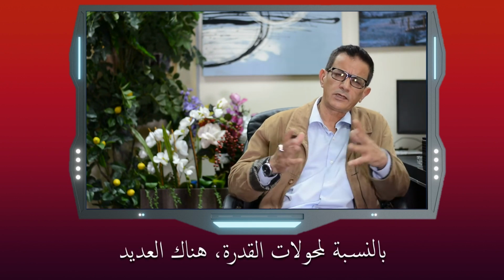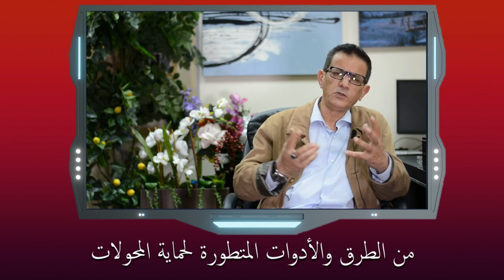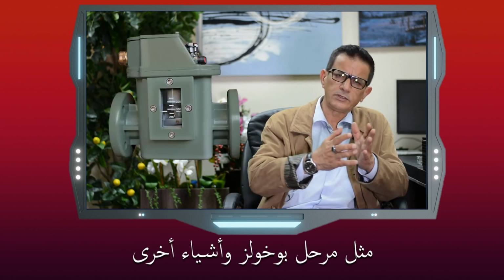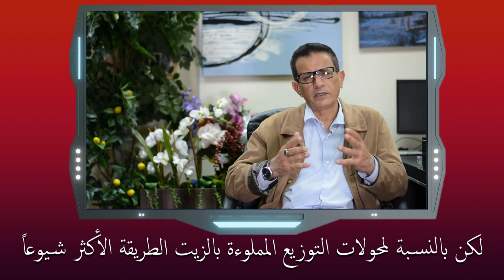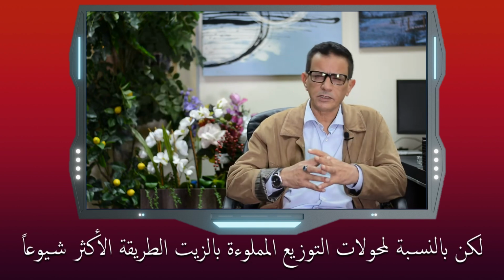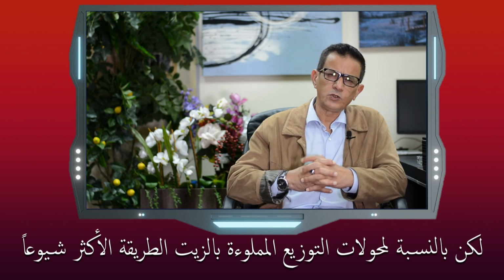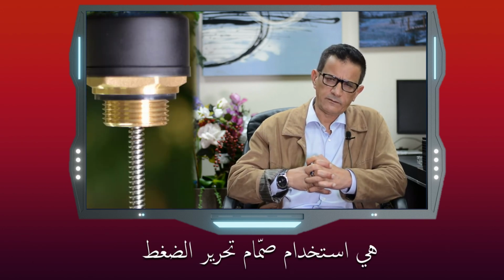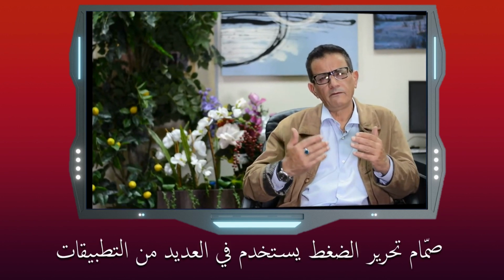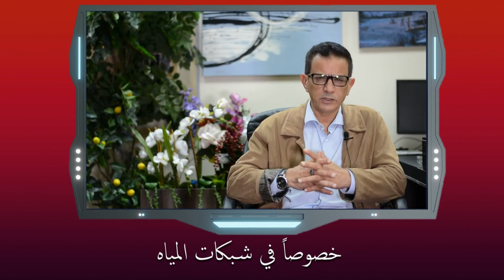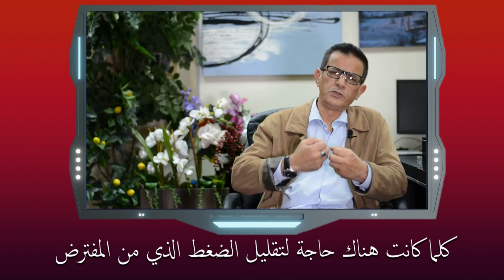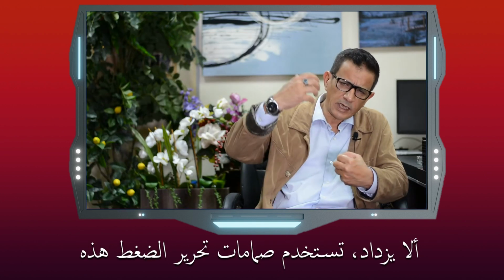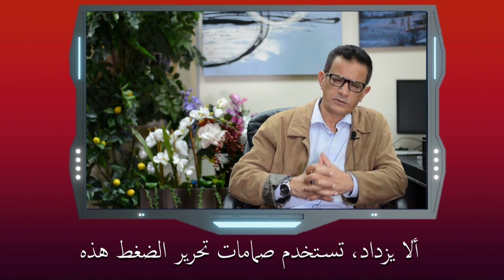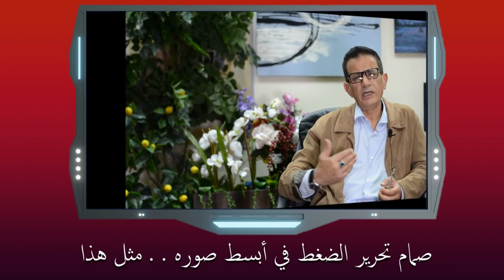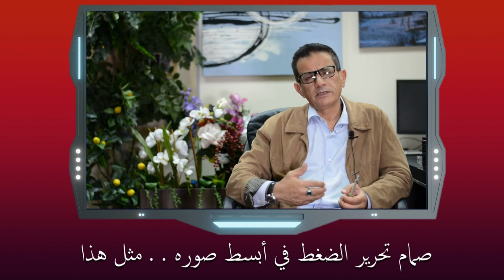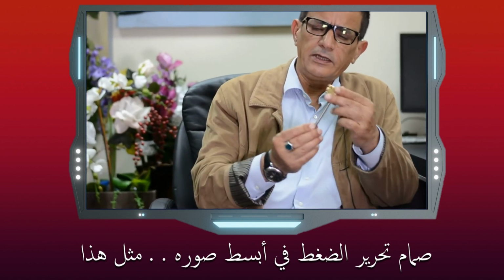For power transformers, there are so many sophisticated aids and tools to protect the transformers, like the Buchholz relay and other things. But for our oil-filled distribution transformer, the most popular thing is to use the pressure relief valve. A pressure relief valve is used in so many applications, especially in water networks. Whenever there is a need to reduce pressure which is not supposed to build up, these pressure relief devices are used.